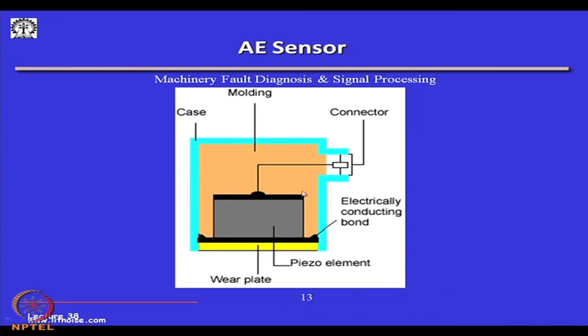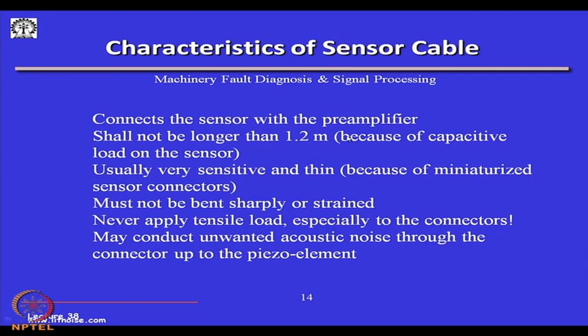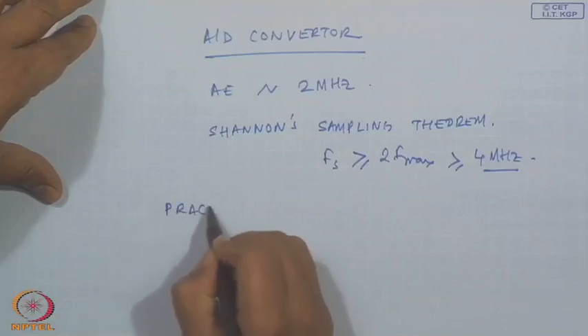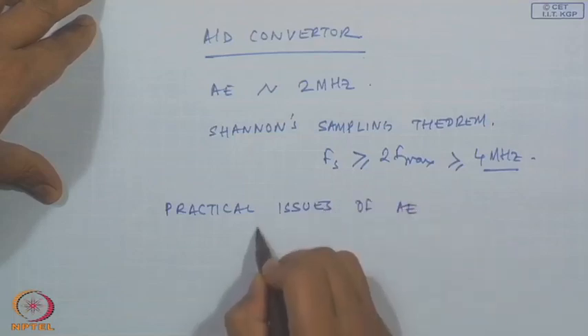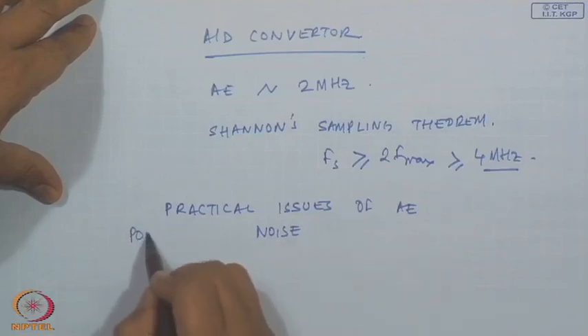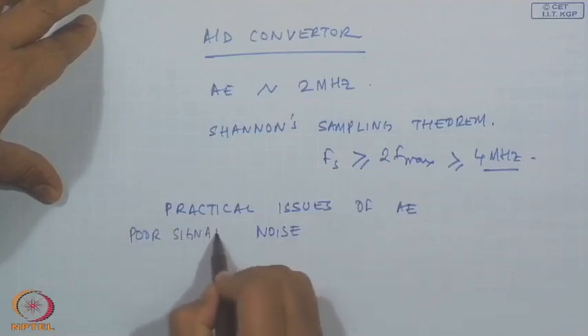An acoustic emission sensor has a piezoelectric crystal which is sensitive to surface waves coming through the structure. These will give a signal corresponding to the stress waves. Because these are all capacitance-based, we have to be very careful regarding noise, and poor signal-to-noise ratio is one of the important practical issues of acoustic emission.